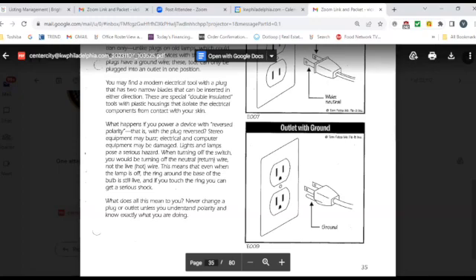If the property has reverse polarity, where that outlet was installed by a non-professional, that's the only time you're going to have a home inspector identify outlets with reverse polarity. Reverse polarity is when the wires are crossed. So what happens? Stereo equipment may buzz, electrical and computer equipment may be damaged, and lights and lamps pose a serious hazard, because when the switch is turned off, it would turn off the neutral or return wire, not the live hot wire. So the live hot wire is still on, even though the light switch is off. See how that's dangerous?